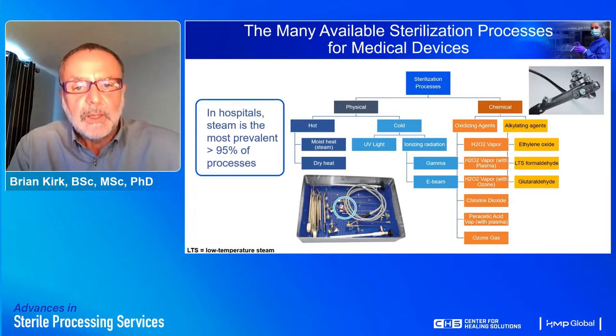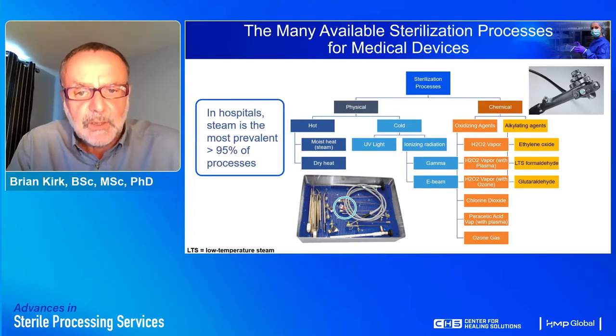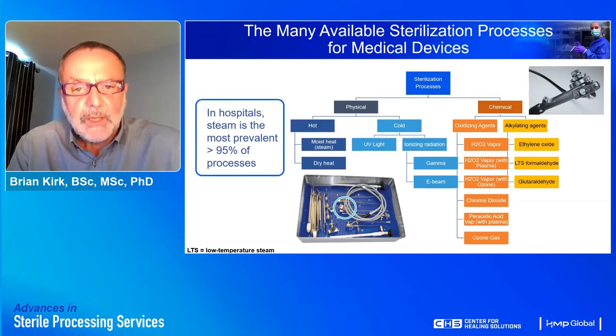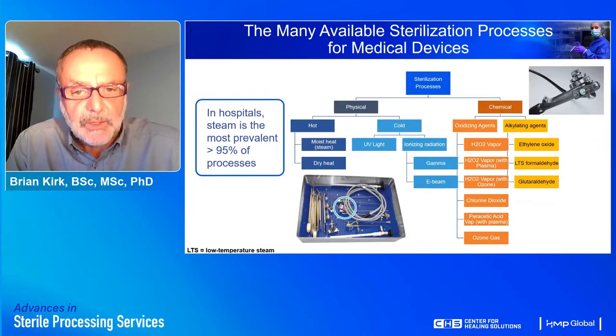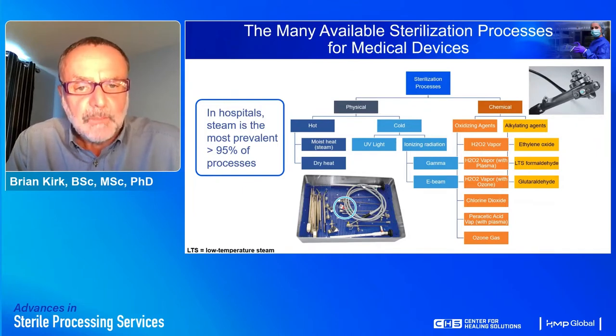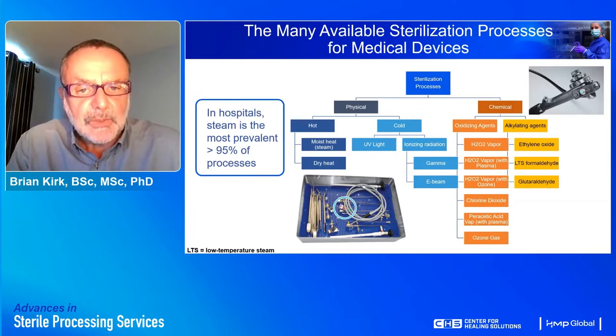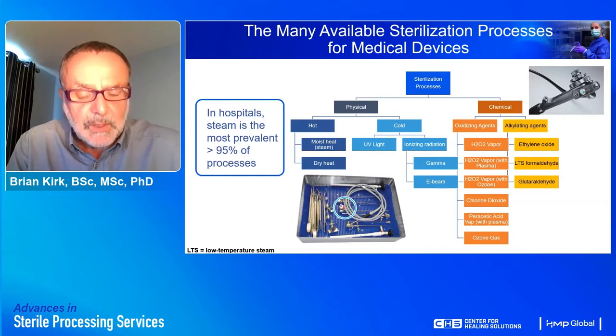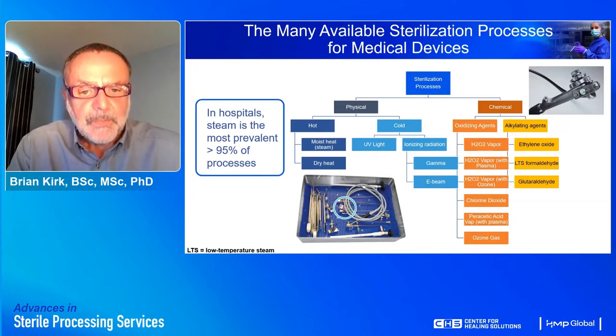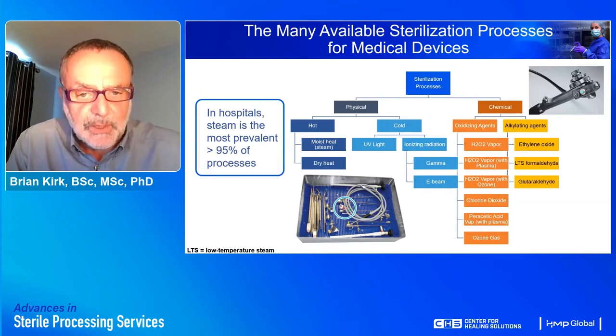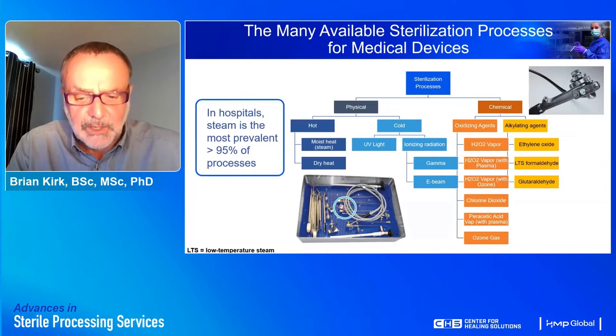We also have chemical microbicidal agents, including the alkylating agents — ethylene oxide, low temperature steam with formaldehyde, and glutaraldehyde — and the more modern oxidizing agents, which include hydrogen peroxide vapor sterilization processes with and without plasma and incorporation of other microbicidal agents. More esoteric agents include chlorine dioxide, peracetic acid vapor, and ozone gas.